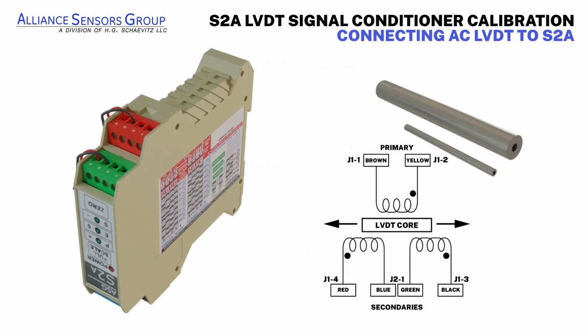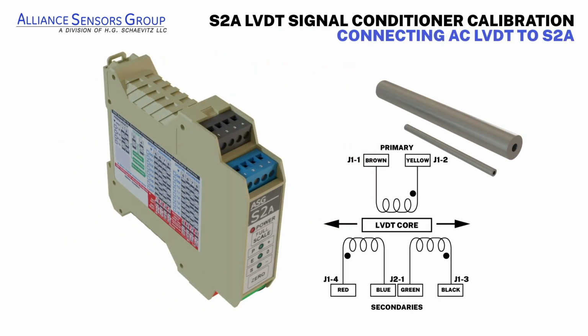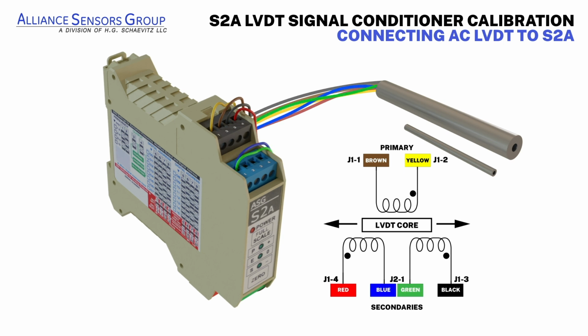When connecting the LVDT, attach the primary high of the LVDT to terminal 1 of the J1 black terminal plug and the primary low to terminal 2. Then connect the secondary 2 high of the LVDT to terminal 3 of the J1 black terminal plug and attach the secondary 1 high to terminal 4 of the black plug. The 2 remaining secondary wires must be connected together and can be attached to terminal 1 of the J2 blue plug for convenience if the leads are long enough. If you're uncertain about the LVDT connections, make the secondary connections using the 2 magnetic dots as your guide.